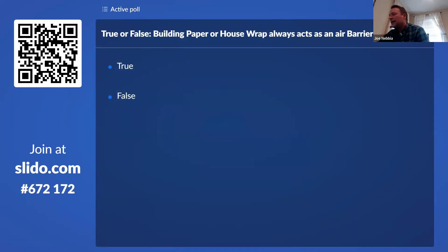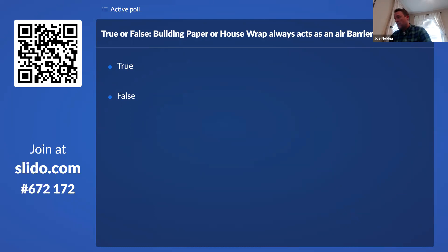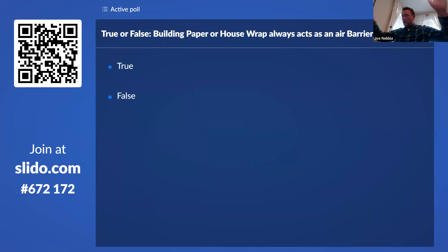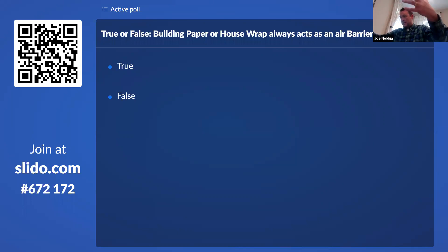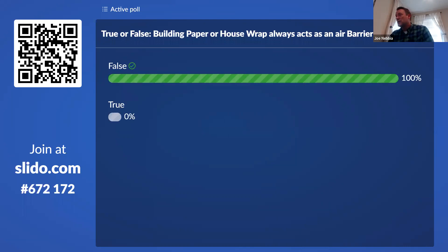Final question: is building paper always an air barrier? Sometimes it's installed as a weather barrier only, and there are different installation instructions based on whether you're installing it as an air barrier or a weather barrier. If you're using it just as a weather barrier, typically you leave the bottom unsealed and untaped so any water that gets behind it can run out. But if you're using that building paper as the air barrier, it needs to be taped. The answer is no — it's not always going to be an air barrier. It can act as an air barrier if installed in a certain way.